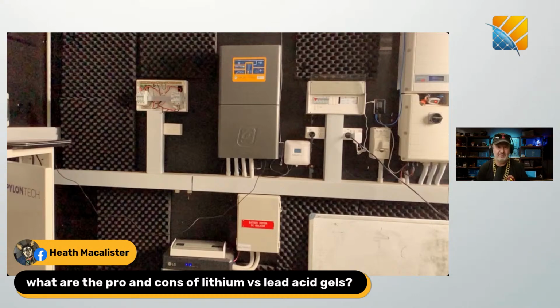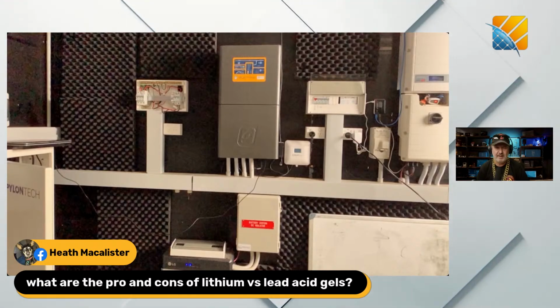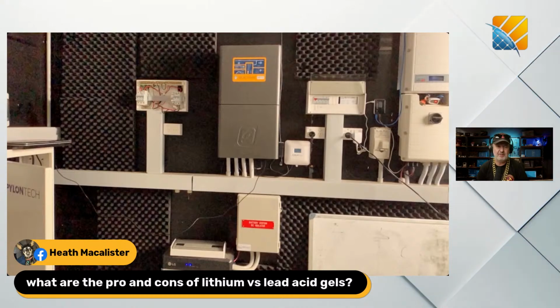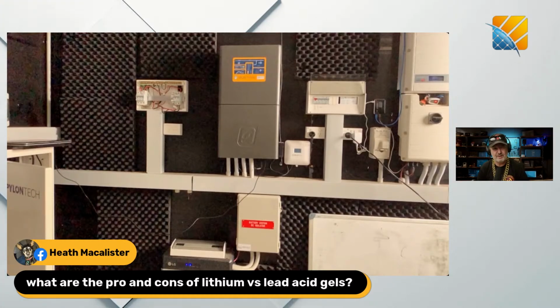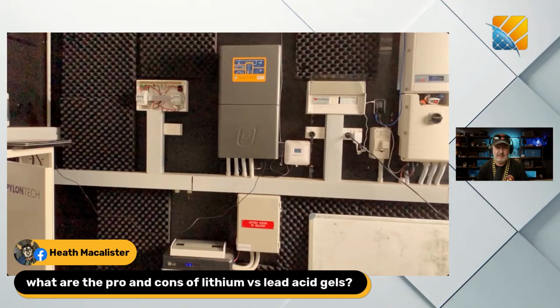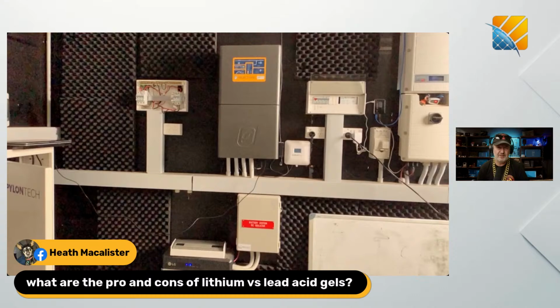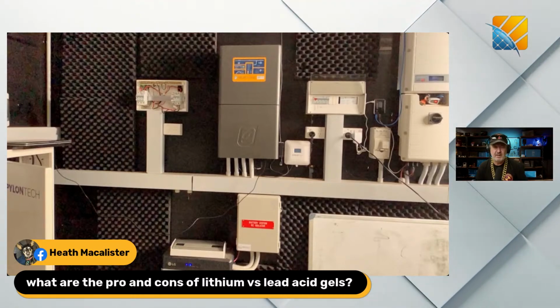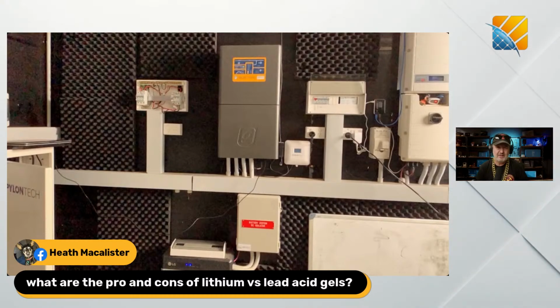But it has its shortcomings. Some of those are short cycle life compared to modern technologies like lithium, and maximum depth of discharge is much more restrictive - typically 50%, maybe 60% maximum depth of discharge to get a healthy life out of a well-designed lead acid battery. So you have to keep that reserve capacity you try never to use. They're heavy, and they're generally designed for off-grid as 2-volt cells connected in series, and they can't be upgraded. So if you've built a system out of 2-volt cells - let's say a 48-volt system with 24 cells in series - 5 years later you want more capacity, you can't just add another string or another battery, because you can't mix old and new. It's bad for both.